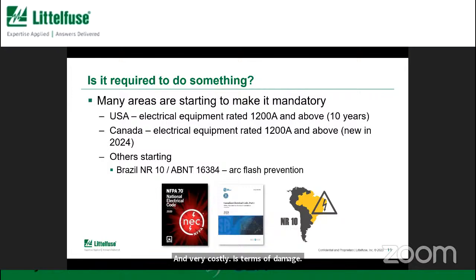So when we look at reducing the energy of an arc flash, of course it makes sense, but there always are questions about whether it is required. Where is this required, or in the law? A lot of areas are beginning to make arc reduction a part of the mandatory electrical code, and put it into the actual laws. In the US, for around 10 years, that has already been in the law. In Canada, that was added this year, in 2024. And Brazil has also had a requirement in NR10 for quite a few years to take measures towards arc flash prevention and mitigation. So it is understood to be a risk, and the number of areas where it's put into the law that you have to do something to reduce the energy is growing.